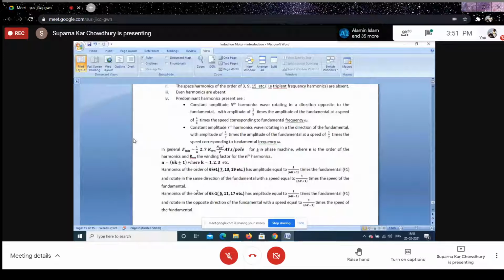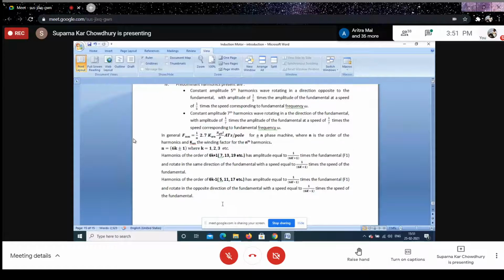Harmonics of the order 6k minus 1: if k equals 1, that gives the 5th, 11th, 17th harmonics, and so on. Their amplitude equals 1/(6k minus 1) times the fundamental, and they rotate opposite to the fundamental, at a speed equal to 1/(6k minus 1) times the fundamental's speed.